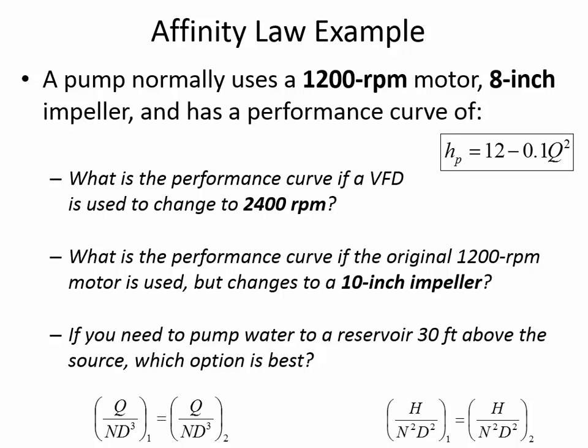So let's say we use a VFD to change it to 2400 RPMs instead of the original 1200 RPM. So what we want to do in a problem like this is find out what the performance curve will look like if we have a different rotational speed. So the original pump curve is H sub P is 12 minus 0.1 times Q squared. And this is at N is 1200 RPM, and the diameter is 8 inches. Okay, so what we want to do is change the N value to 2400. So the original N1 is 1200. We want N2 to be 2400 RPM. We're going to leave the diameter of the pump the same, just spin it twice as fast.